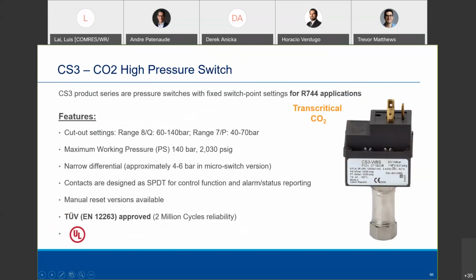This particular one here, you can read it pretty well. It cuts out at 106 bar, cuts in at 80 bar. And there's different models available, of course. The temperature range, -40 to 150 degrees Celsius. That's its temperature range.